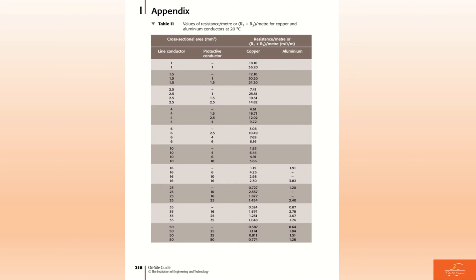In this table, what you actually have in this chart is values of resistance per meter, or what we know as R1 plus R2 per meter, for copper and aluminum conductors at 20 degrees Celsius.